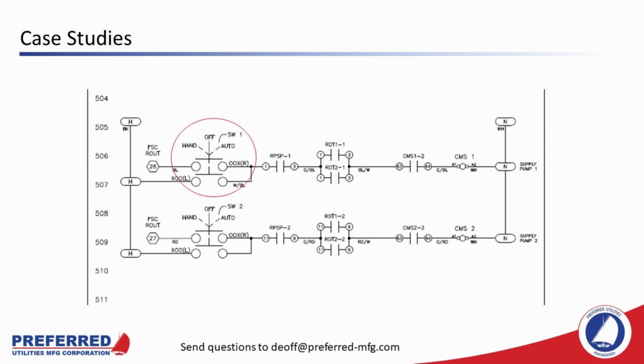These fueling systems are designed to run in automatic. If the system is not in automatic, it's not ready to do its job, and the plant personnel should be made aware. When the generator is shut down because it's sucking air out of the day tank, it's too late.